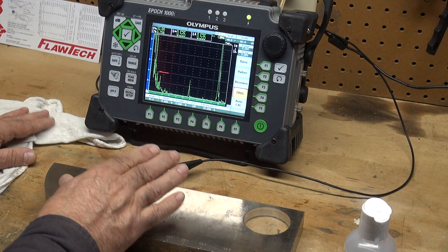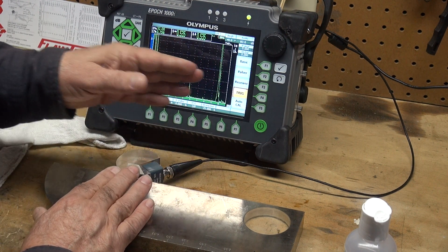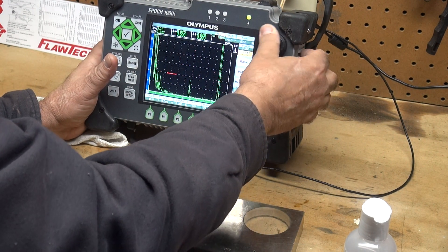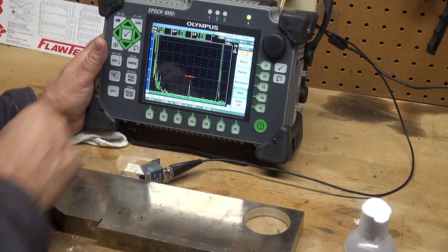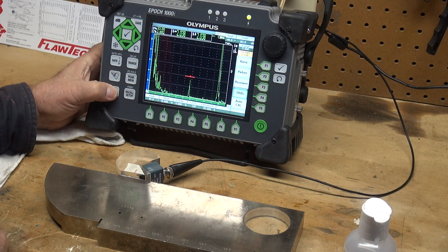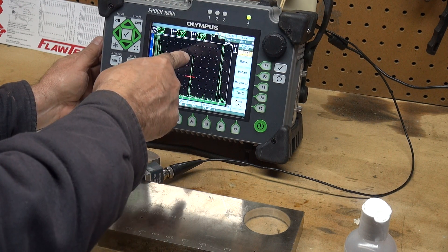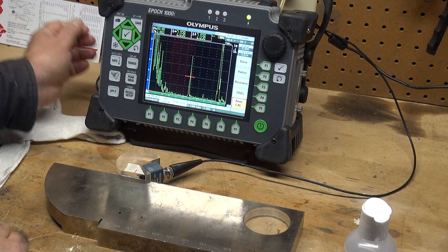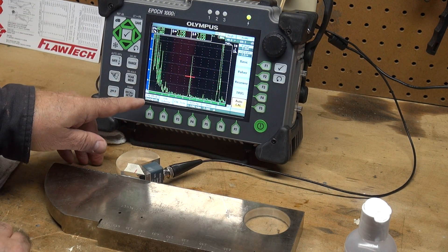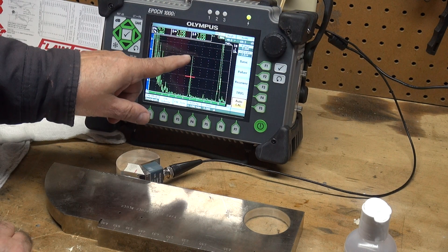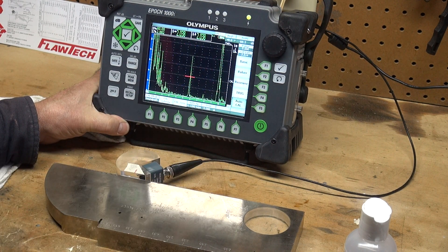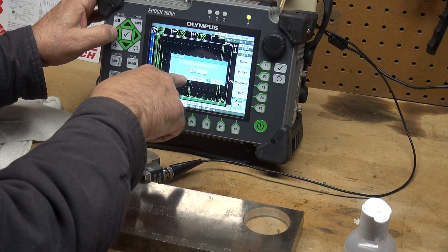Now I want to calibrate. We have this transducer in a position where I'm getting my maximum energy back. I'm going to take my gate, move it over that first reflector, that's the 2 inch radius. I'm going to take it to 80% full screen height using auto 80. I want to push my auto cal button and calibration mode comes up with sound path, cal velocity, and cal zero. I want to press cal zero to calibrate the zero of my machine. The machine wants to know what that value is, so I'm going to change that value to 2 inches.